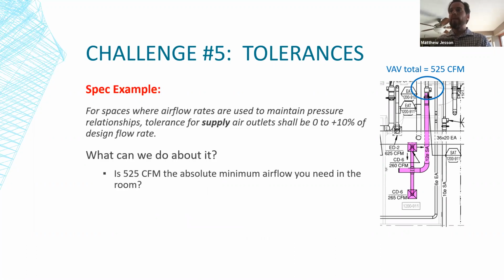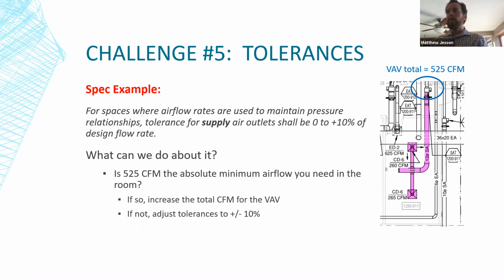So what can we do about that? And this is a question for the engineer really. Is 525 the absolute minimum airflow that you need in the room? Can you not live with 510 CFM? Well, if it absolutely has to be 525 or higher, then it's pretty simple to just increase the total CFM set point for the VAV. And then you can make sure that it always stays above that 525. And if not, I would say just adjust these tolerances to plus or minus 10%.